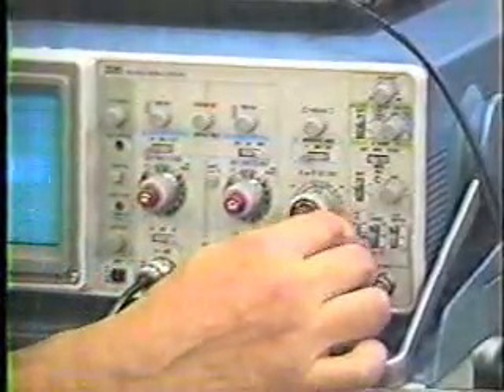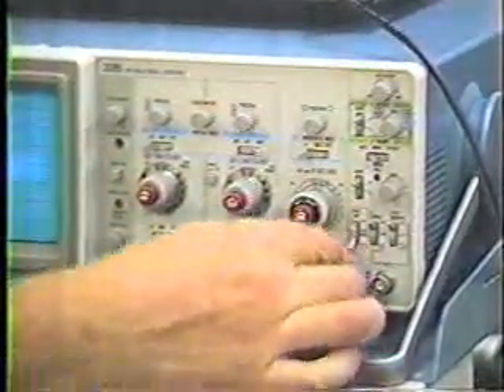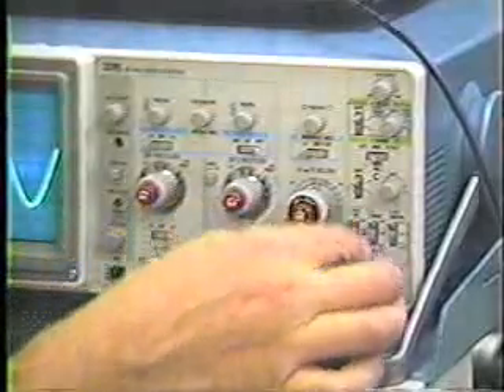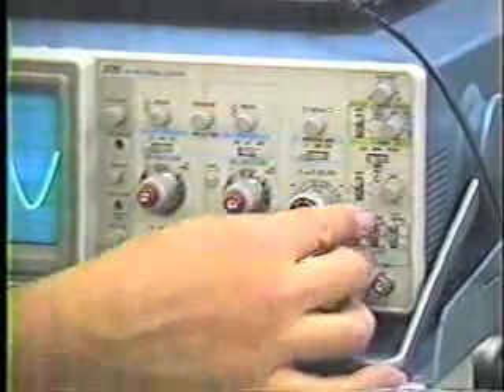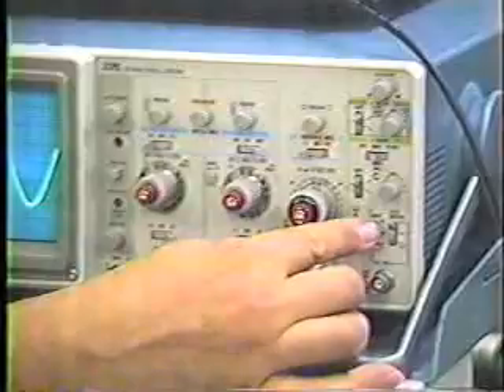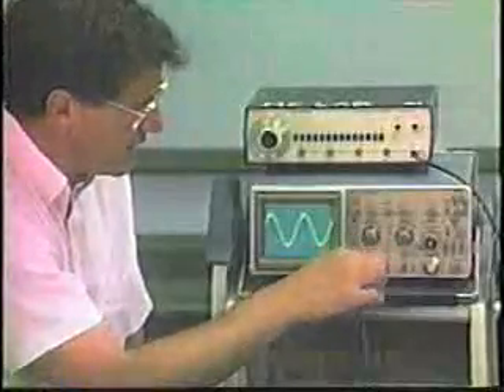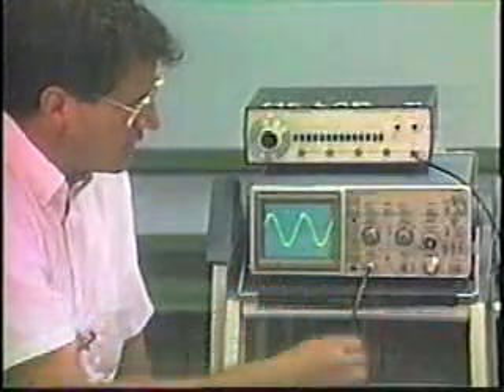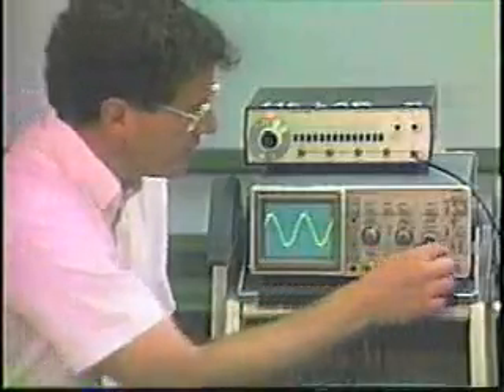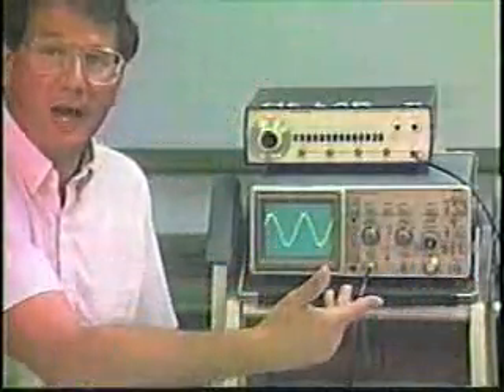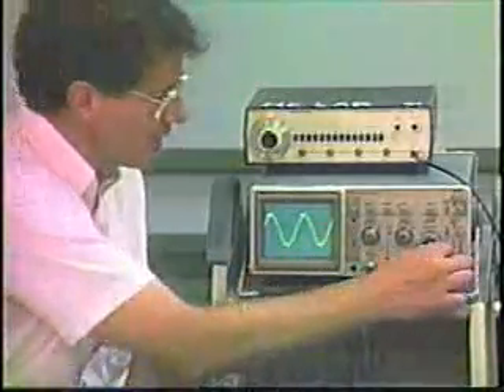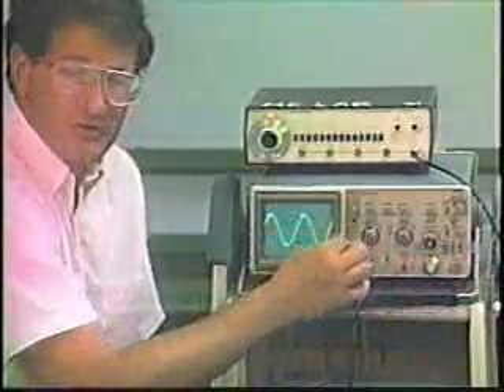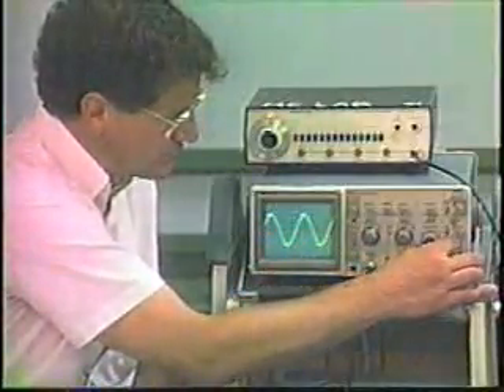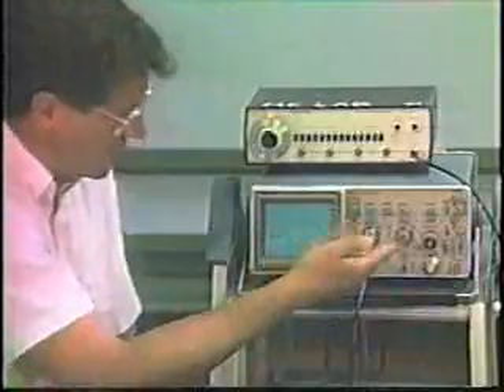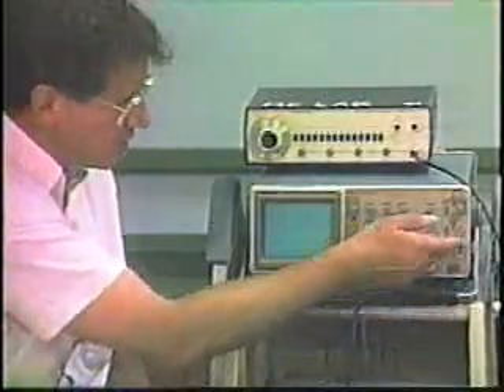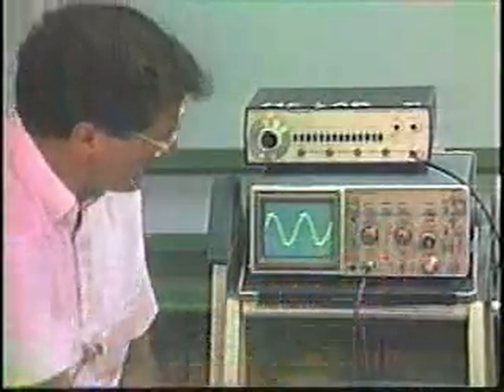If you wanted to trigger on channel 2, you would switch that to channel 2. But in this case, we're on channel 1, and we want to set the second toggle switch to internal, which means it will be triggering internally on the signal applied to the input. We could also have an external trigger that would determine the sweep rate, and we would have to change the switch over here to external, but because we have no external signal, that makes the signal disappear.